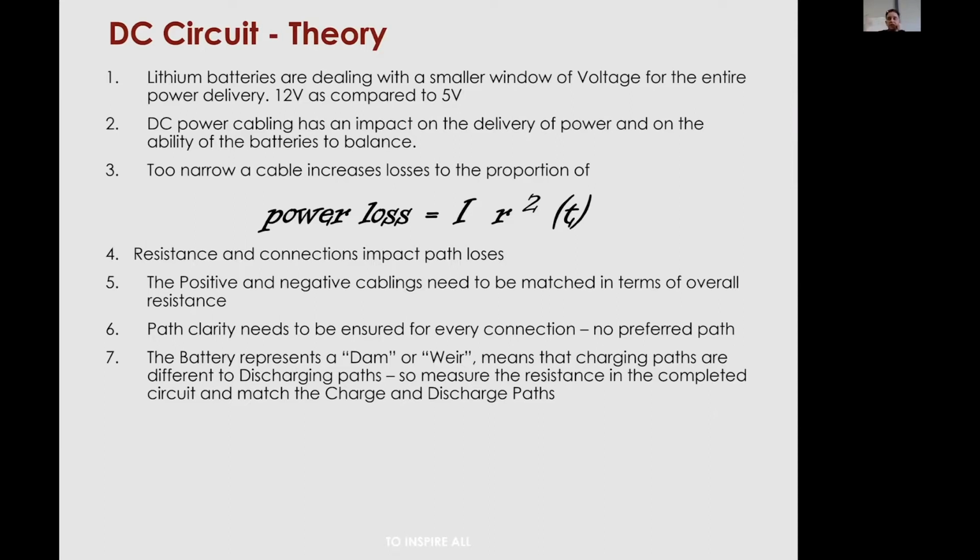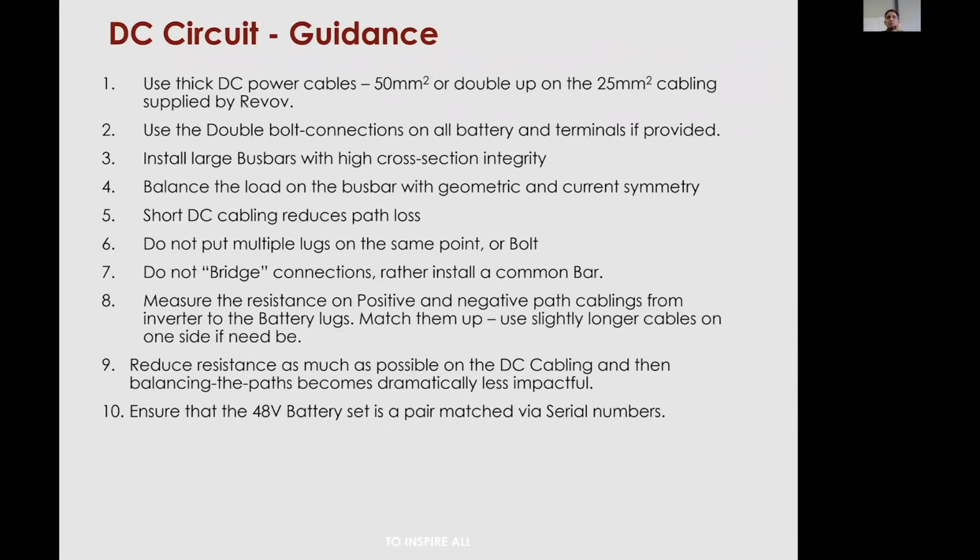And with those little pointers, it's actually quite simple as to what the impact is in terms of your installation. So using those same points, all you do is you do a couple of things. Make sure that your cables are thick, 50 millimeters, or double up on 25 millimeter cable or 35 millimeter cable.